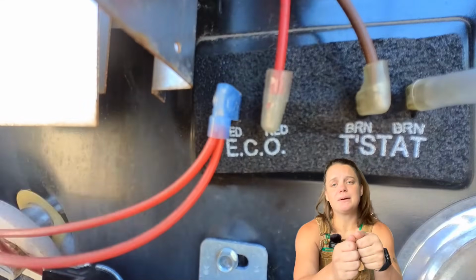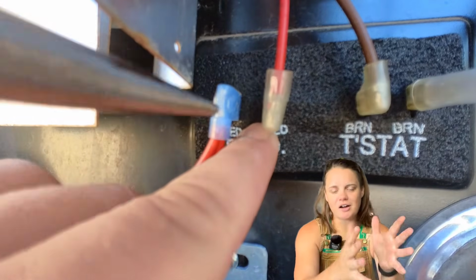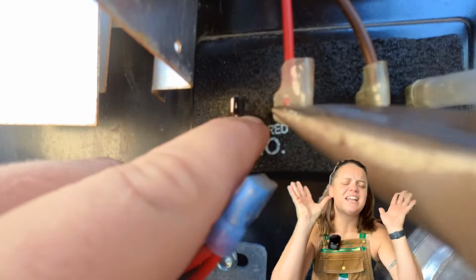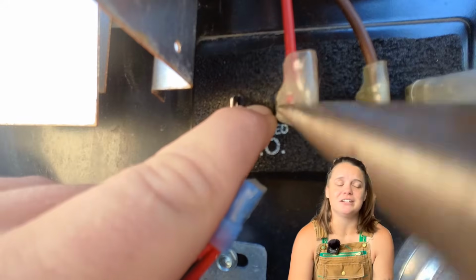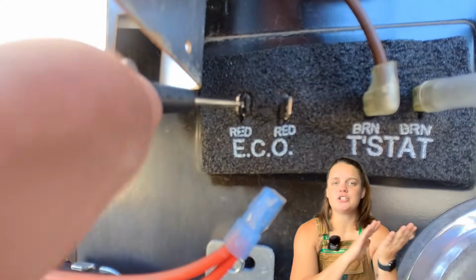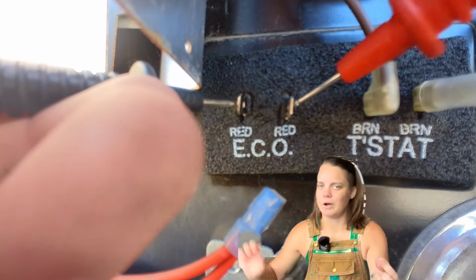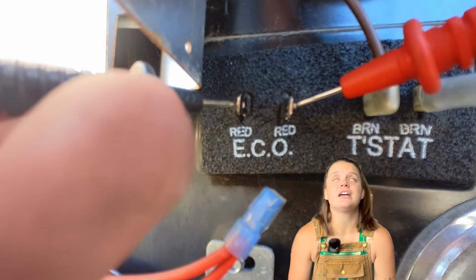We can double check this the same way we checked the T-stat: remove both terminals off of the ECO so it's naked and separate from the circuit entirely, then set your meter to continuity and put one probe on each side of the ECO. If we hear a beep, the ECO is good and we need to double check our work. If we do not hear a beep, the ECO is bad.